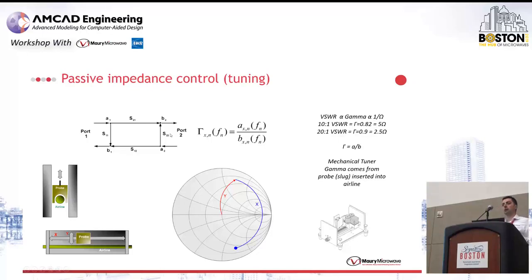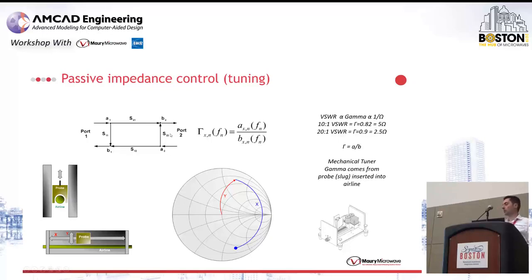Mechanical tuners are quite nice because they're simple to use, robust, and can handle very high powers. They do have limitations — specifically, it's a passive instrument, so the A wave coming back onto your device under test will always be lower than the B wave. This means you cannot cover the whole Smith chart, which is especially important with very large devices. They can also be rather slow because they must move mechanically with a motor for every single impedance.